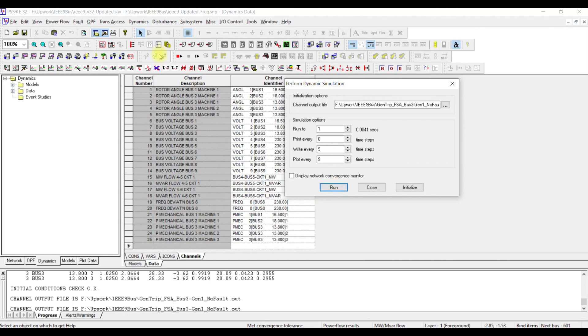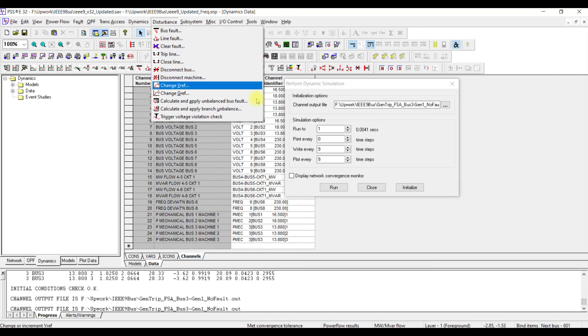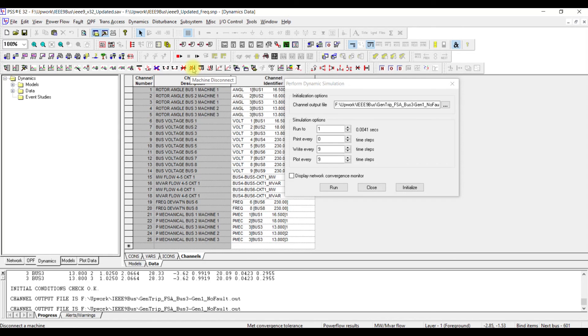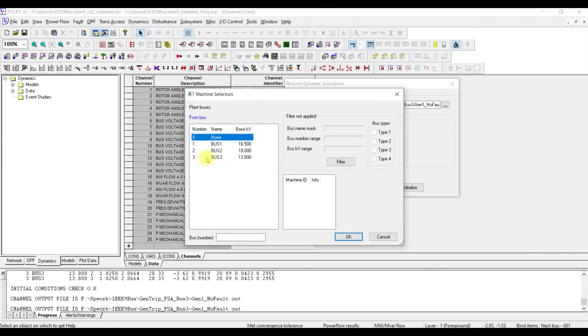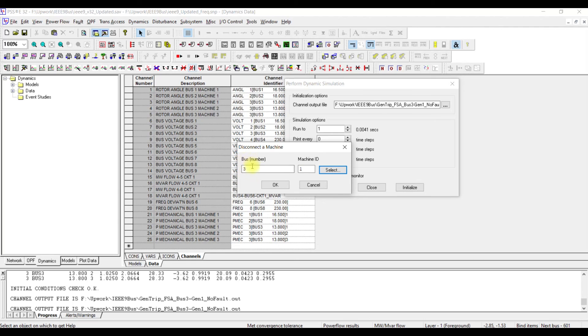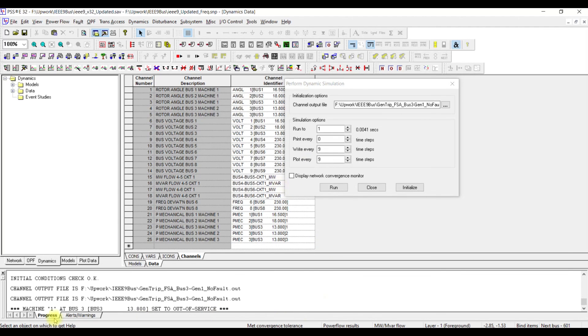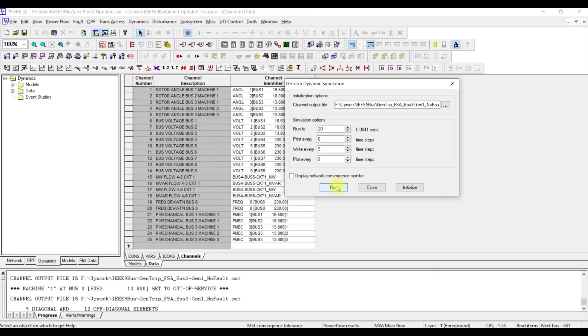The system has run for one second. Now to trip the generator, go to Disturbance > Disconnect or use the toolbar machine disconnect option. Selecting machine disconnect, I enter bus number 3 and machine ID 1, then press OK — machine 1 at bus 3 is set out of service. Since frequency stability takes longer than rotor angle stability, I will run the post-disturbance simulation for 20 seconds so all governors and controls can respond. I enter 20 and press Run.